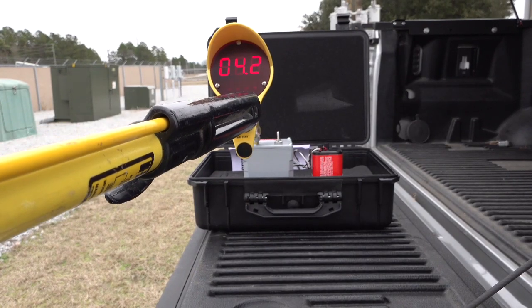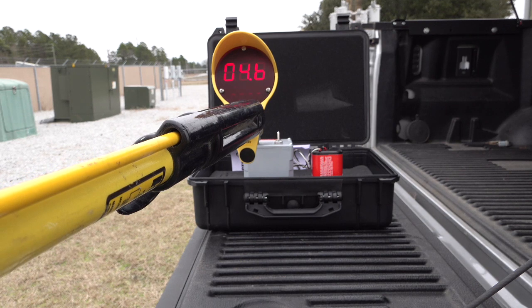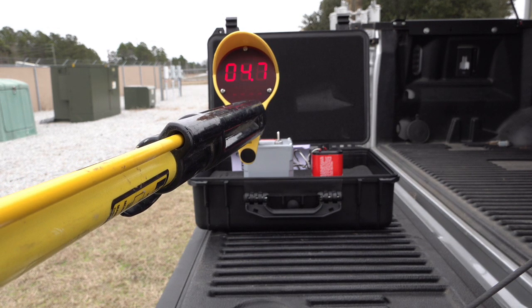We also highly recommend that you test the VD1000 on what's called a known voltage. A known voltage test will test 100% of the meter and determine if the meter is functioning properly or not. In this example, we are using a 3 kV power supply, which is an optional accessory for the VD1000. You'll notice the reading is 4.7 kV, which is a nominal voltage. We will discuss later in the video what nominal voltage means. Once you have completed the known voltage test, now the VD1000 is ready to be used.